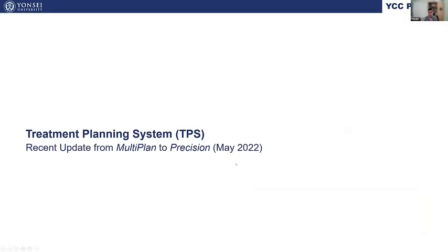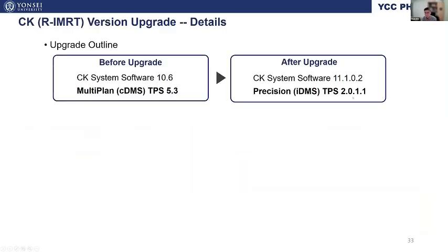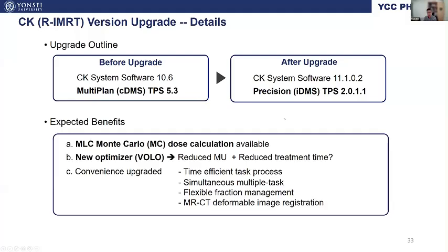Thus far, I have been focusing on the QAs for hardware, but I'll move on to the treatment planning system, which was recently upgraded in our institution. The upgrade was made in 2022, which took about 5 weeks, including firmware and software upgrade, followed by additional QA processes, including annual path calibration and E2E tests, and some part of beam commissioning for the new dose calculation algorithm. We've got numerous benefits from the upgrade in terms of dose calculation algorithm, plan optimization, and some additional functionalities. Basically, the Precision TPS upgrade made every task faster.